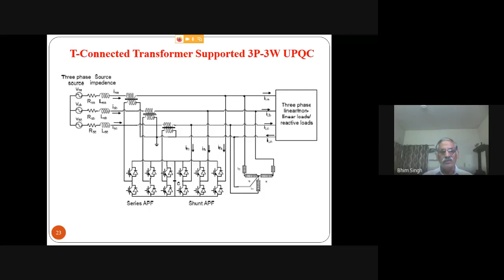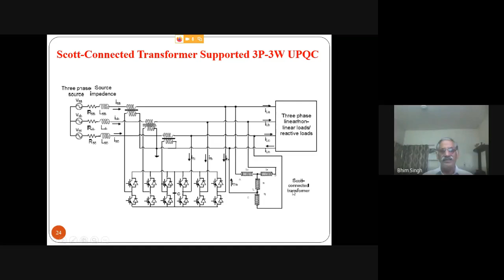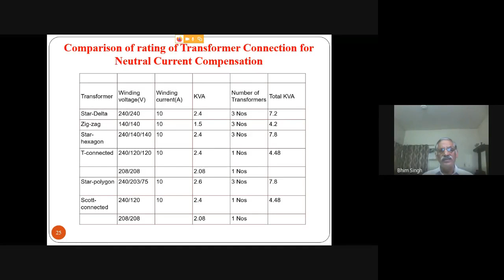But certainly zigzag is preferred because the VA rating of zigzag is much lower than all other topologies. The benefit of using the T connection or Scott connection is only that you have 2 single phase transformers, whereas for zigzag you have 3 single phase transformers. That's another benefit you can think about. Students should work out all those, what are typically the benefits or demerits for neutral compensation with different transformer connections, and the rating calculation also. So that was about the power circuit configuration, which I mentioned.